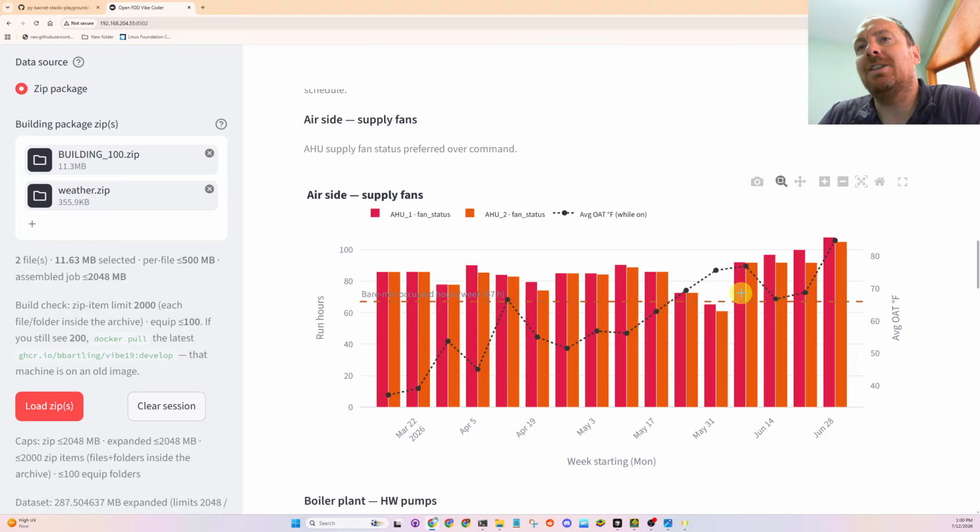every day. So the hardest thing, the optimal start, sounds really easy to do, but in reality it's rarely implemented. If you're a facilities manager out there and you know that your building is optimized like this, hats off to you. I never see this. It's very, very rare. It's a really hard algorithm to just set it and forget it. It's one of those that someone needs to be maintaining.